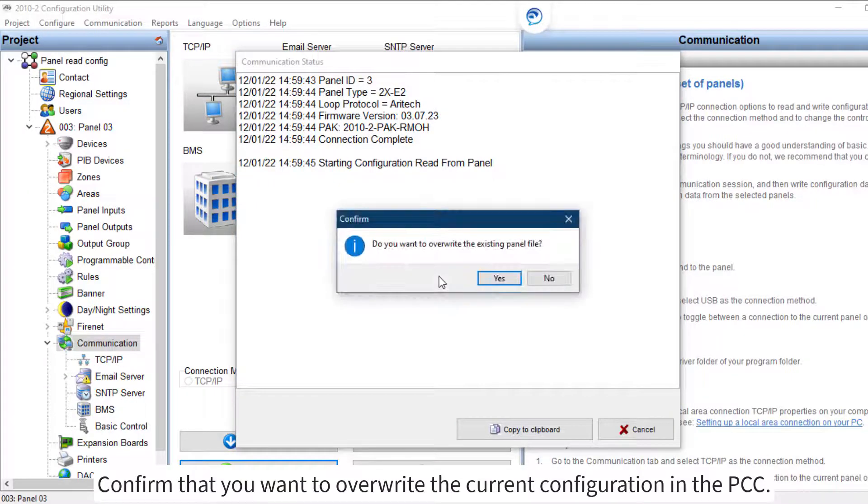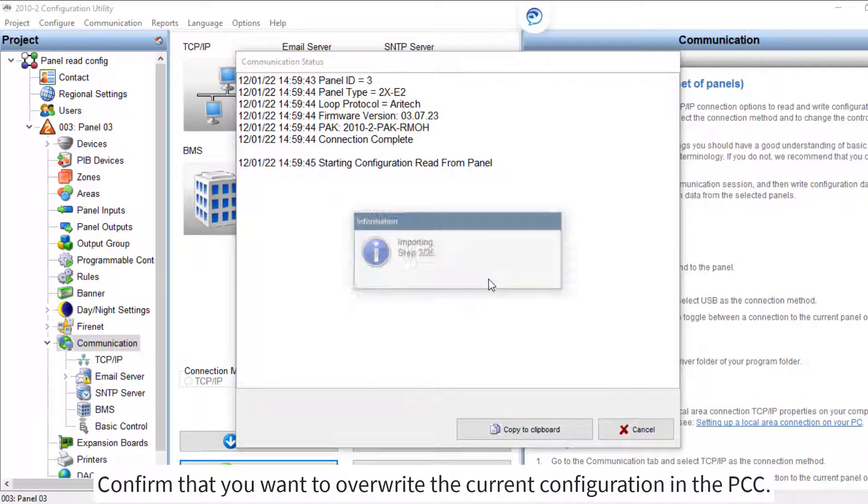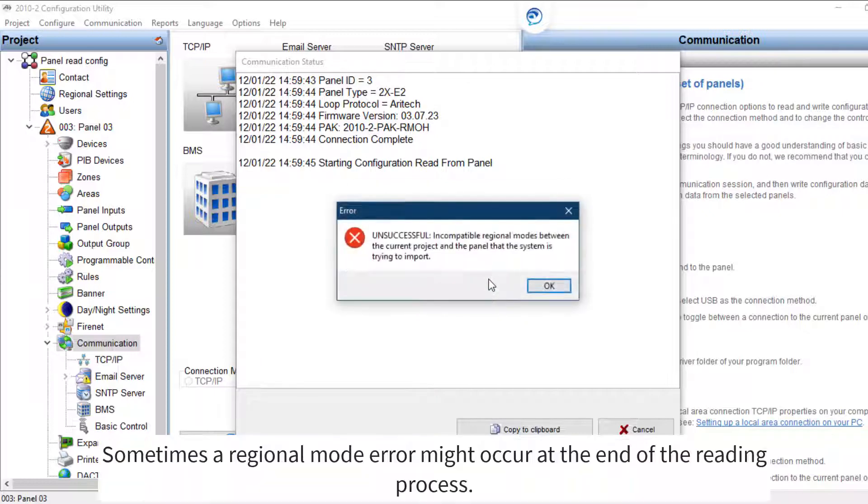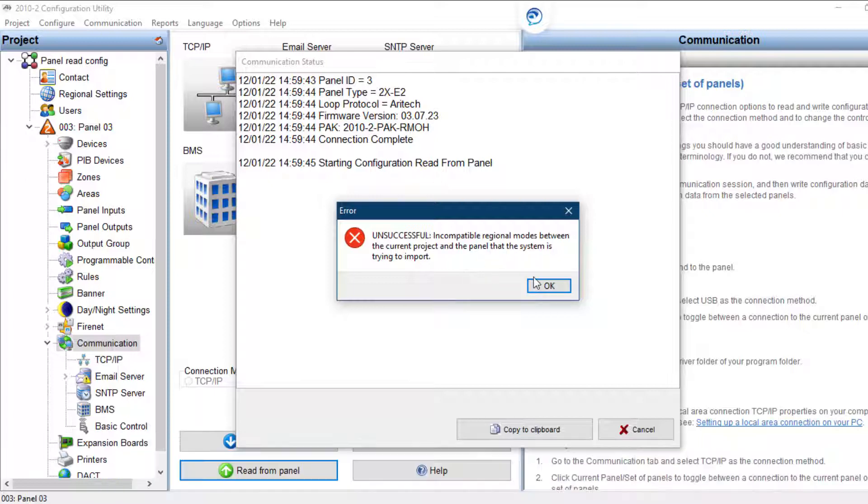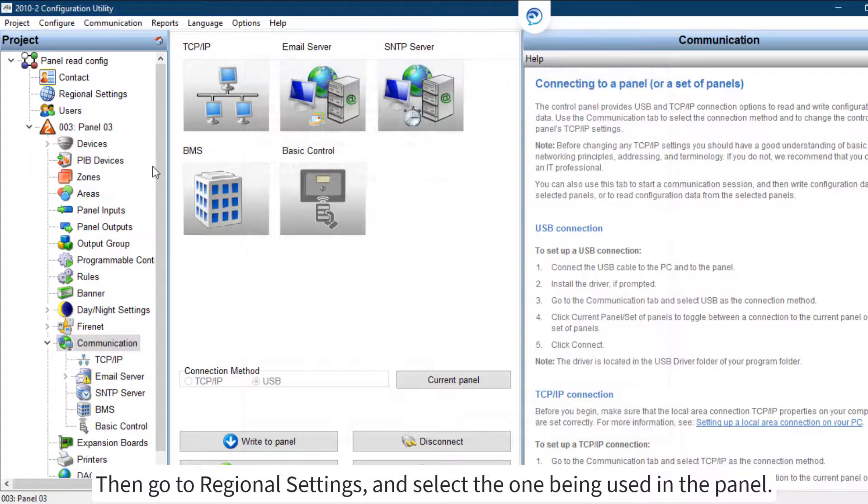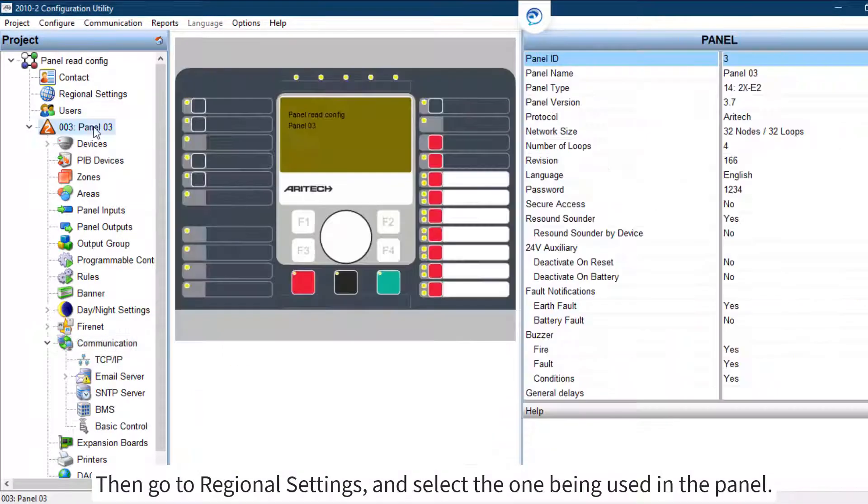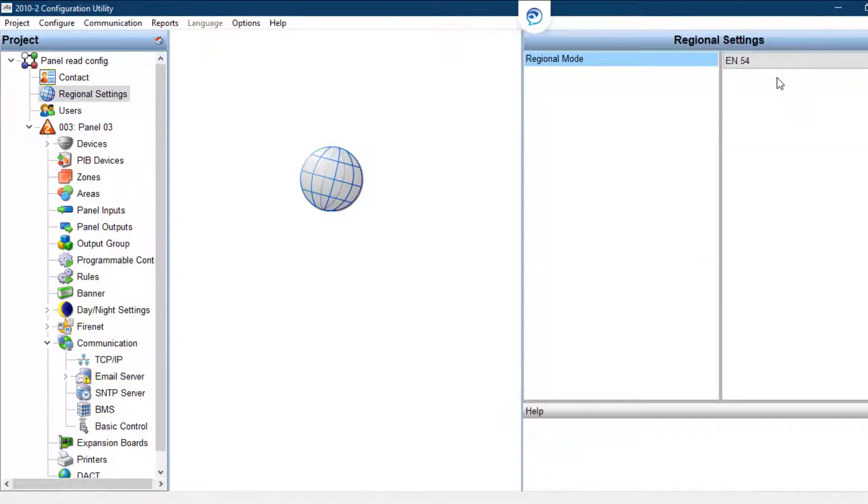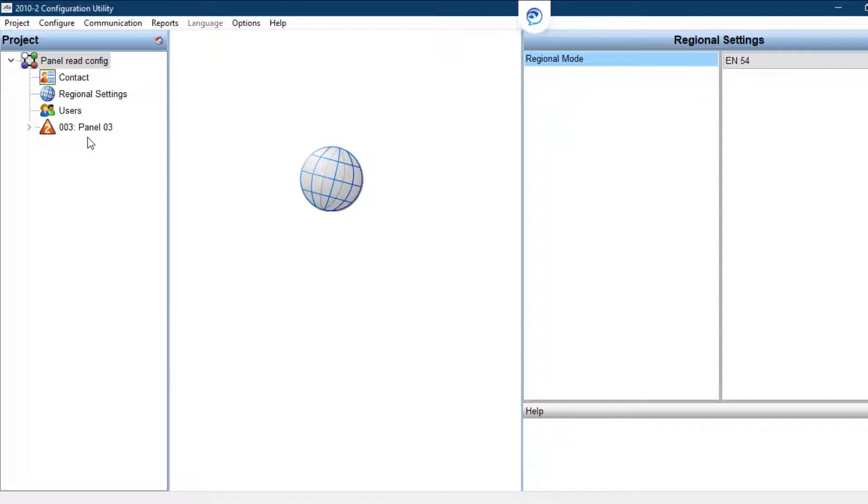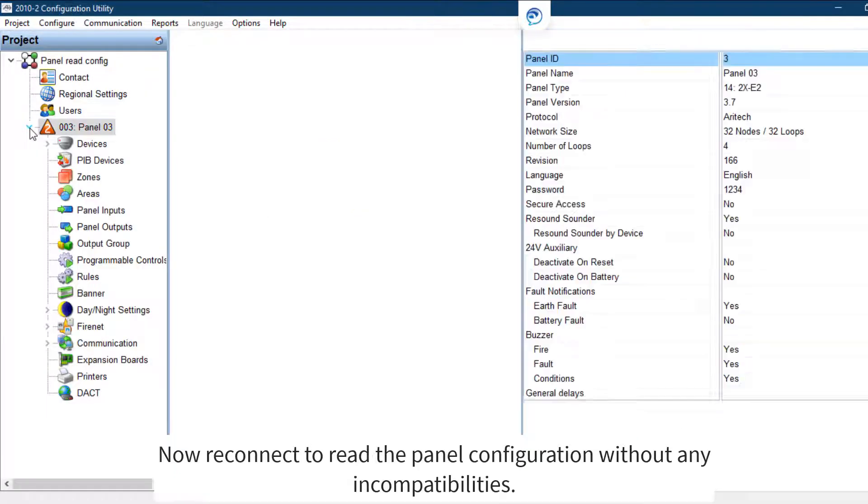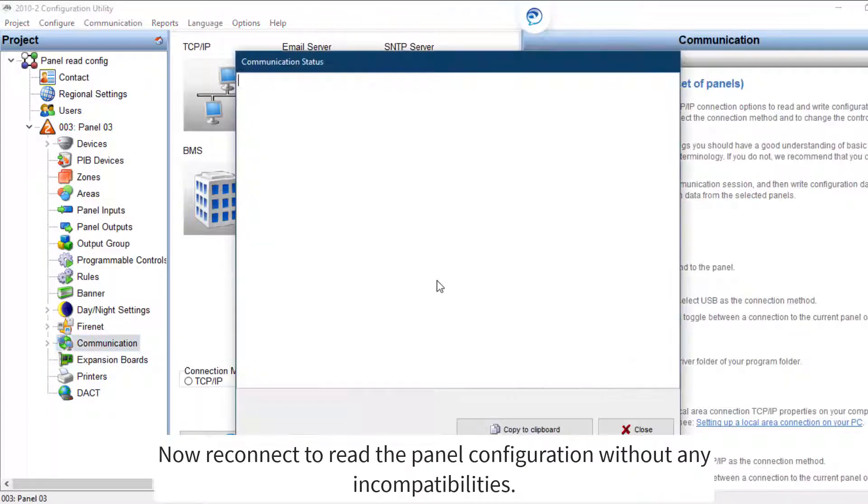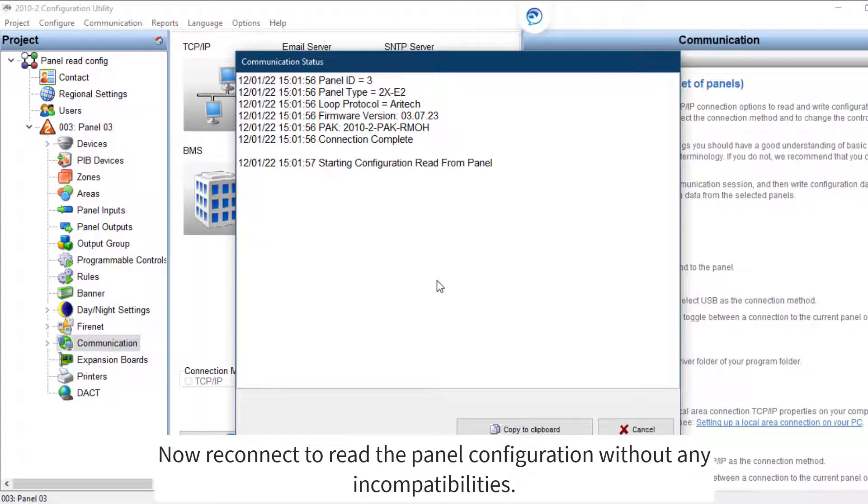Confirm that you want to overwrite the current configuration in the PCC. Sometimes a regional mode error might occur at the end of the reading process. Then go to Regional Settings and select the one being used in the panel. Now reconnect to read the panel configuration without any incompatibilities.